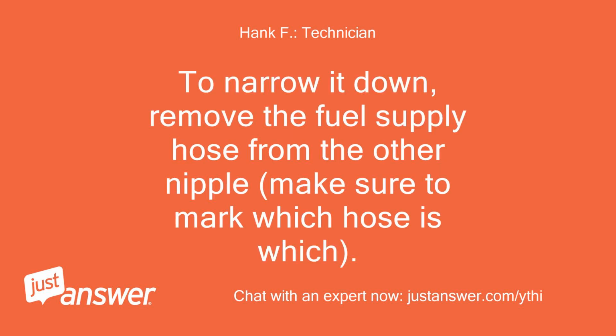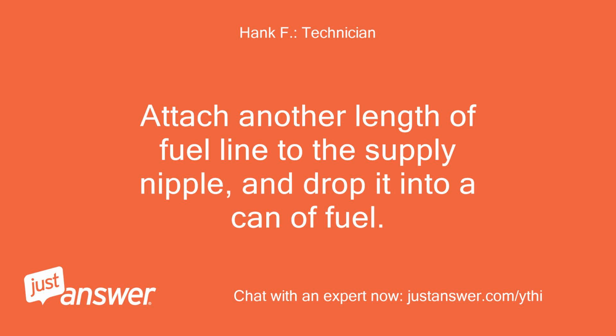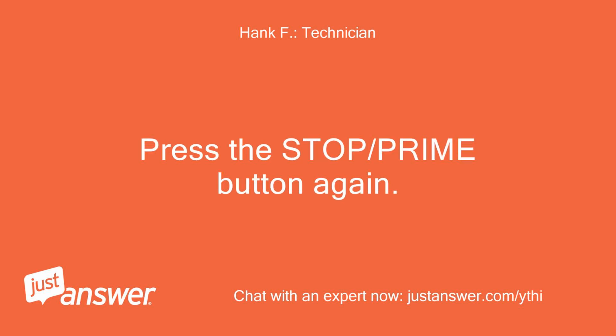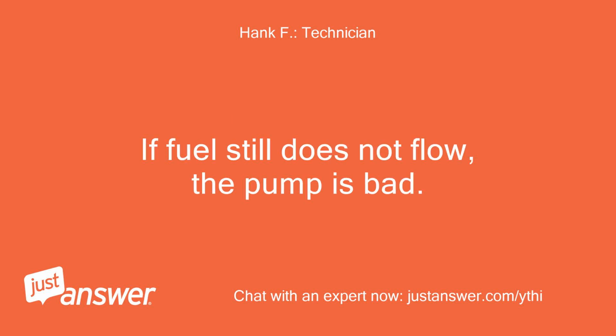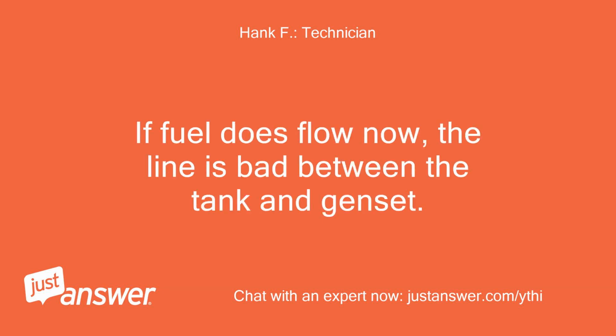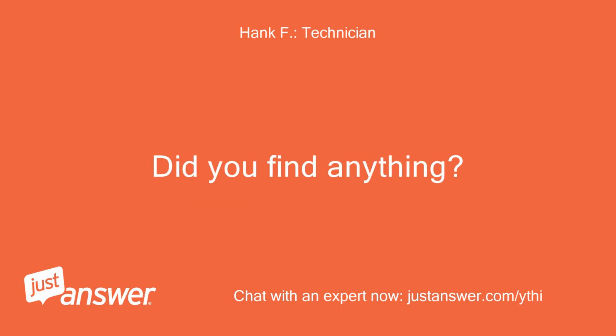To narrow it down, remove the fuel supply hose from the other nipple. Make sure to mark which hose is which. Attach another length of fuel line to the supply nipple, and drop it into a can of fuel. Press the stop/prime button again. If fuel still does not flow, the pump is bad. If fuel does flow now, the line is bad between the tank and genset. Did you find anything?